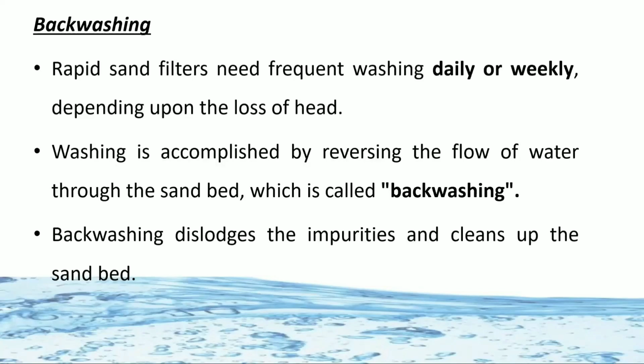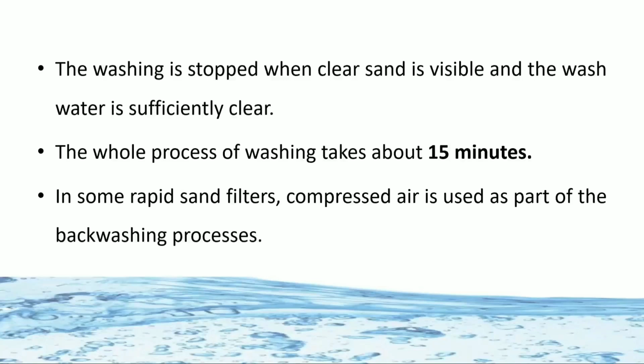Backwashing dislodges the impurities and cleans the sand bed. The washing is stopped when the clear sand is visible and the wash water is sufficiently clear. The whole process of washing takes about 15 minutes. In some rapid sand filters, compressed air is used for backwashing.